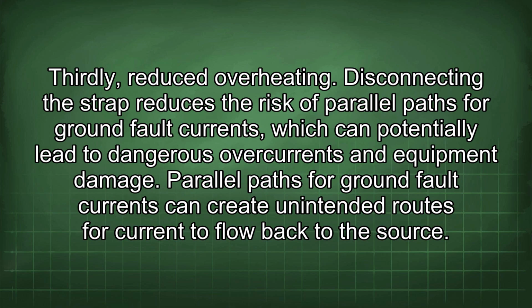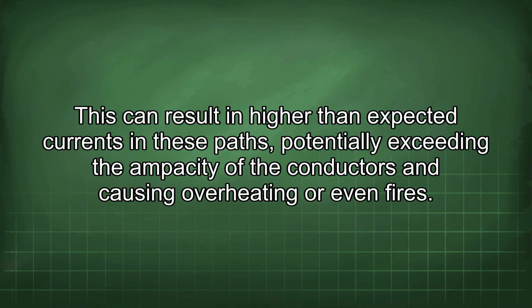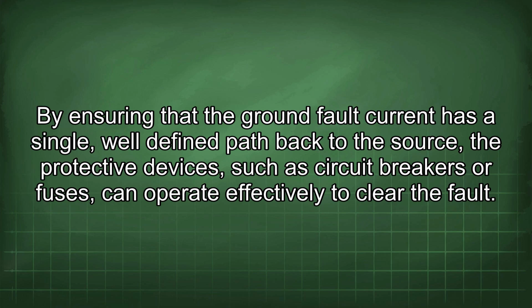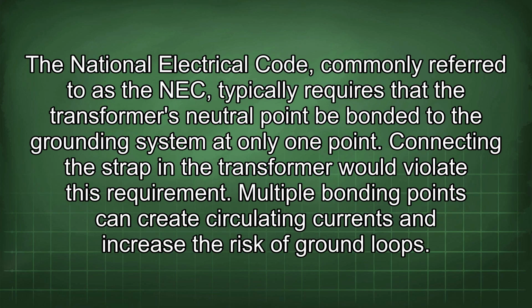Parallel paths for ground fault currents can create unintended routes for current to flow back to the source. This can result in higher than expected currents in these paths, potentially exceeding the ampacity of the conductors and causing overheating or even fires. By ensuring that the ground fault current has a single, well-defined path back to the source, the protective devices, such as circuit breakers or fuses, can operate effectively to clear the fault. The National Electrical Code, commonly referred to as the NEC, typically requires that the transformer's neutral point be bonded to the grounding system at only one point. Connecting the strap in the transformer would violate this requirement.